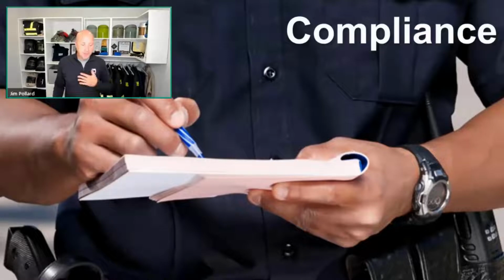If you're joining us from Canada, then there's even more changes that apply to Arc Flash PPE in the 2021 edition of the CSA standard. That's the CSA Z462. And just one of those changes that's much different and doesn't exist in the US is an Arc Flash PPE Category 5. So if you're sitting on a program that hasn't been updated in a few years, you have either a little bit of work to do or you have a lot of work to do. So it's something to be aware of.